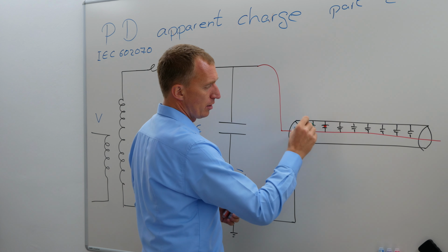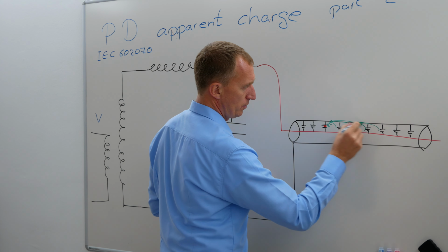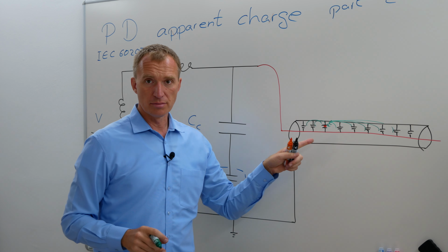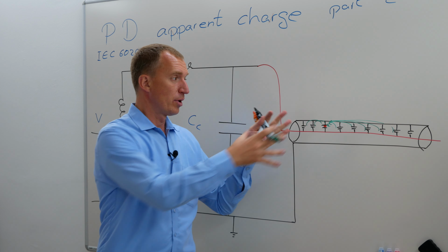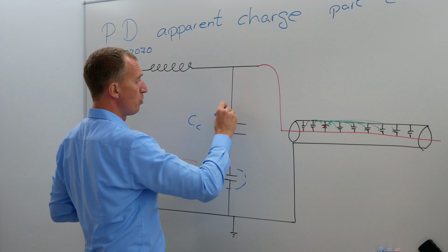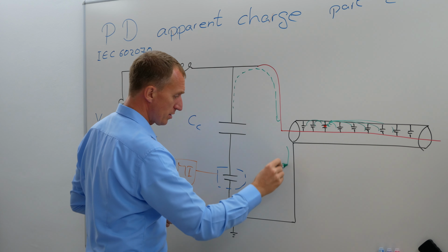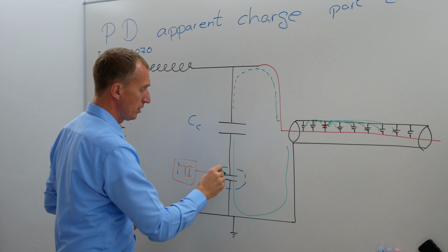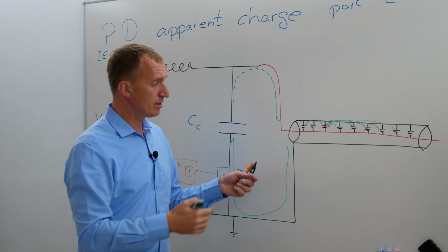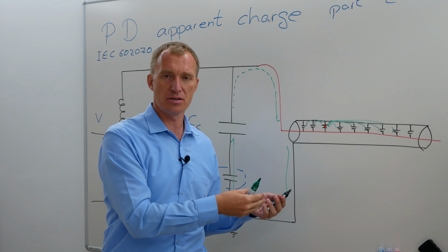We're going to have a charge loss here, and this capacitance will recharge, and this one, and I mean, obviously, you're getting the idea. And now, after all of these are recharging the missing charge, only a portion is allowed to go in here. The problem is, this is the only current that goes through my quadripole. So this is the only one I can measure. Thus, I never really know how big the partial discharge inside my test object is.